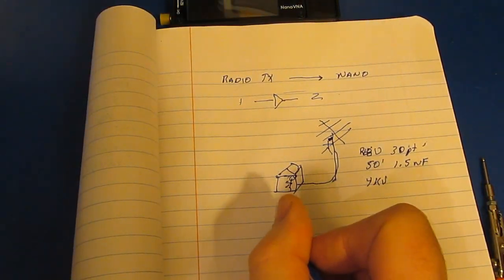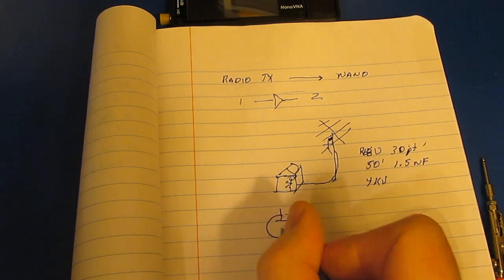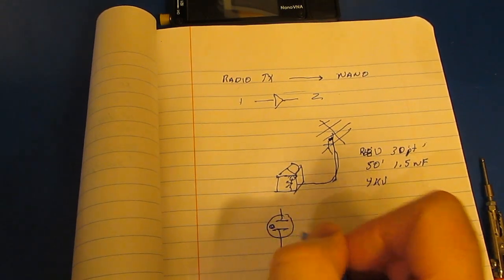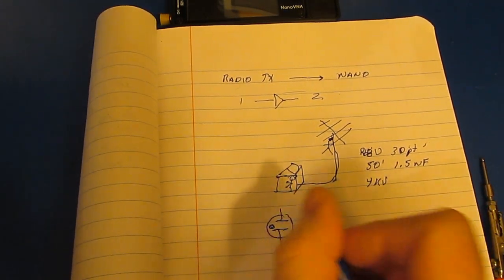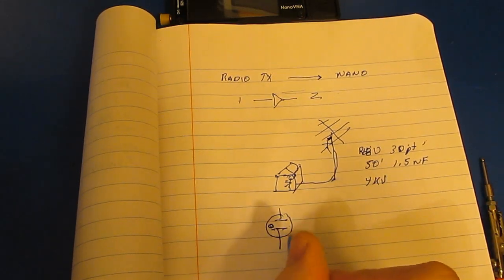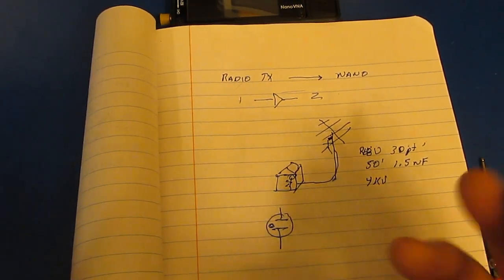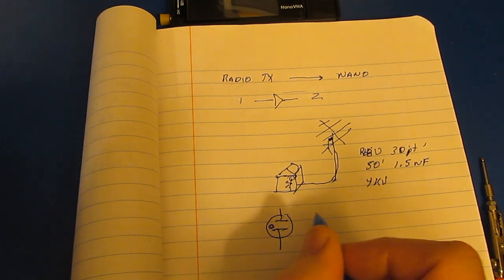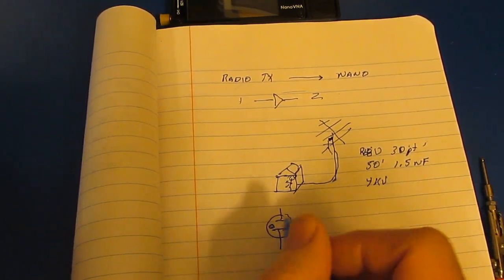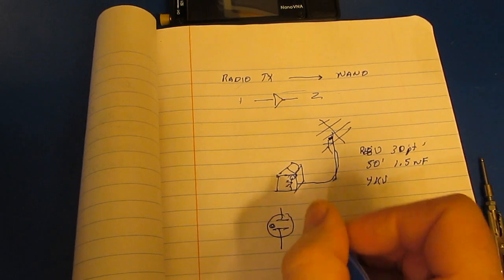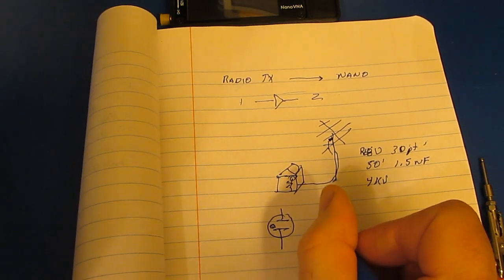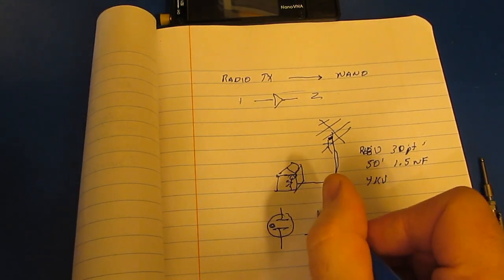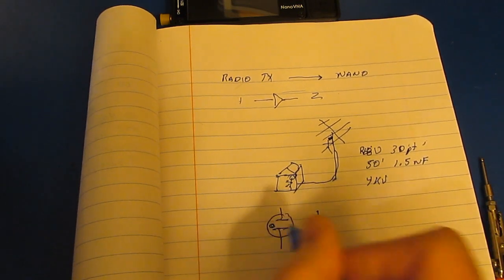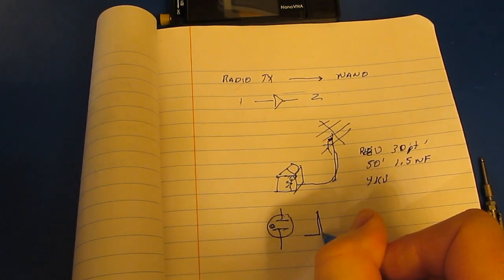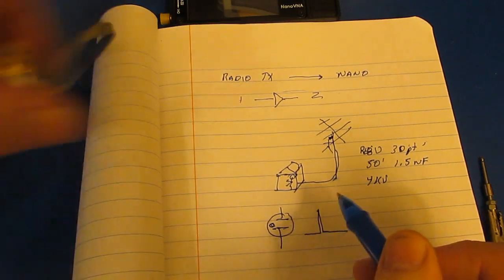Let me talk about that a little bit. A gas discharge tube is literally a tube filled with some kind of gas. It was even pretty common to use neon bulbs for transient protection. You can buy these tubes in different shapes and sizes, with different ratings for voltage breakdown as well as the amount of energy they can dissipate. Essentially what happens is the voltage climbs up to whatever the breakdown is, and this thing starts to conduct, it breaks over, and becomes a dead short. So once these fire, it's a very low impedance path.